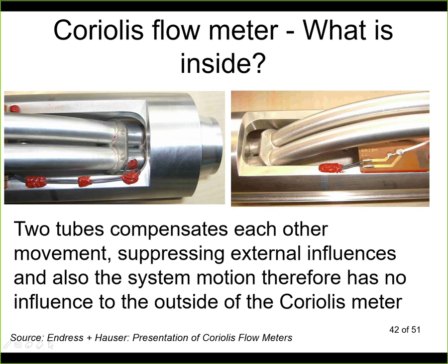Inside it looks like this. So here we can see the stainless steel pipe like that, two pipes. Here we can see the different sensors, so it may be a temperature sensor. Somewhere here there will be the driving coil. Here you can see a part of the electronic circuit in the driving coil, so there will be the driving coil somewhere here, and somewhere here there will be the actual position sensors.